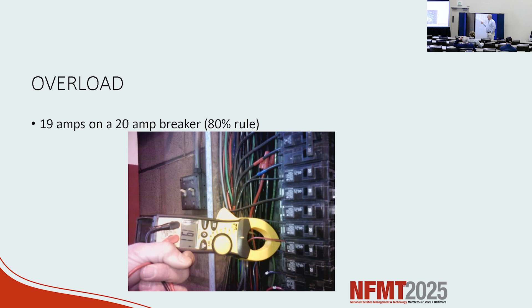Typical loose connections are faults. Overload — does anybody know the electrical rule for maximum load on a circuit? It's 80 percent. A 20 amp circuit with a 19 amp load is an overloaded circuit. That's the kind of thing we'll see with thermography.